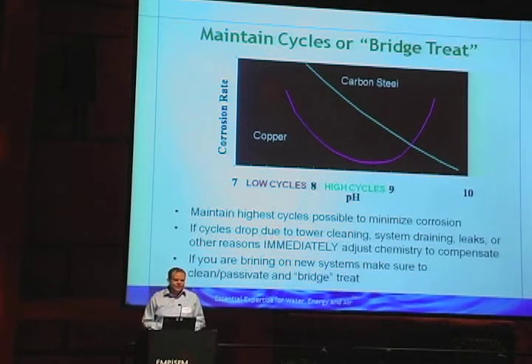New systems. Kind of a side note, any sort of new construction project you've got, or anytime you're going to add a new chiller, add a new tower, add some new piping to your condenser systems, I see this a lot, especially in new construction, they do the commissioning, they'll fill it up with water, then they'll just let it sit there. Maybe they'll circulate it every once in a while just to test out the control systems, but that's it. That's when you're going to get the most corrosion, is that fresh city water just sitting in those pipes. So if you ever have an instance during the off-season or during a new construction project where you're bringing on a new piece of equipment, make sure you get on top of that real quick.